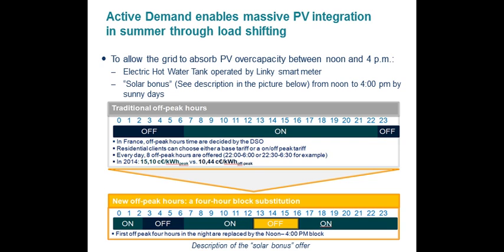In summertime, to encourage customers who live in an area where PV production could be a problem, EDF, the supplier and retailer, has put in place two offers. The first relies on a remotely controlled water heater: the water tank is charged, and we switch it on from 2 p.m. onward, when PV installations are most productive. Water heaters are switched on through a dry contact with the smart meter. The water tank is used as a storage asset, able to absorb excess PV generation within the distribution grid.